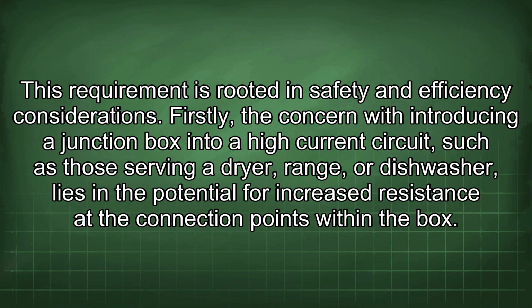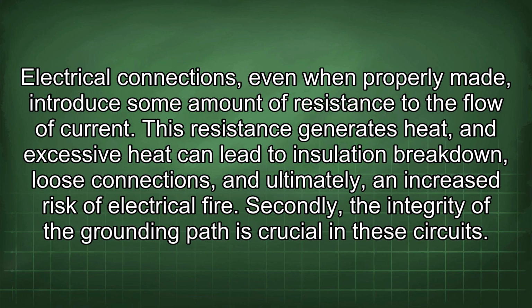Firstly, the concern with introducing a junction box into a high-current circuit, such as those serving a dryer, range, or dishwasher, lies in the potential for increased resistance at the connection points within the box. Electrical connections, even when properly made, introduce some amount of resistance to the flow of current. This resistance generates heat, and excessive heat can lead to insulation breakdown, loose connections, and ultimately an increased risk of electrical fire.